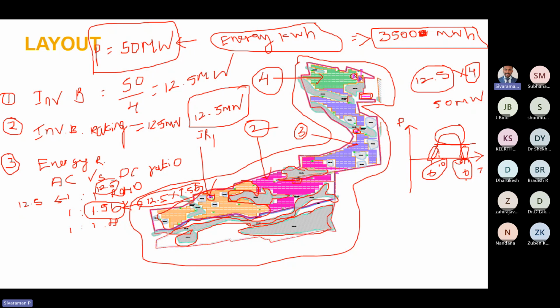Among the 12 hours, for 7 hours in a particular day we have lesser power generation. During that time the solar plant will not produce 50 megawatt. It will produce very little, based on the availability of irradiance. If the power is less, then absolutely the energy produced during these hours also will become less. Due to that we are not able to meet this 3500 megawatt hour of energy.